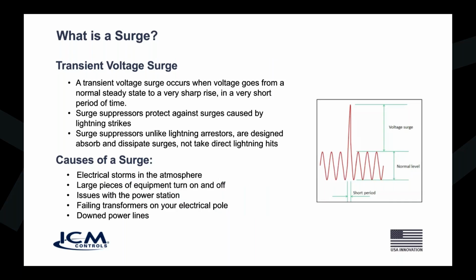Causes for surges can be from electrical storms in the upper atmosphere. Those electrical storms in the upper atmosphere will surge energy down the power lines, which are in parallel with the Earth. So they induce that voltage right into the power lines, and that's where your surge comes in from the power lines. You could also have large pieces of equipment in a factory, for example, turning on and off, creating voltage swings. And not just little voltage swings. I mean, you could be a huge spike when that inrush current comes in and that piece of equipment turns back on.